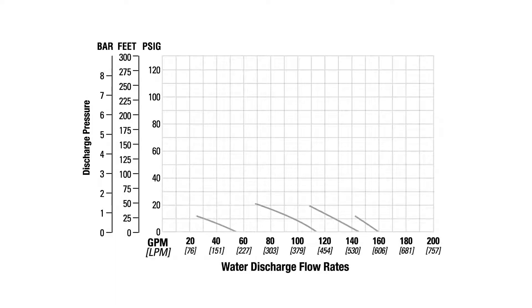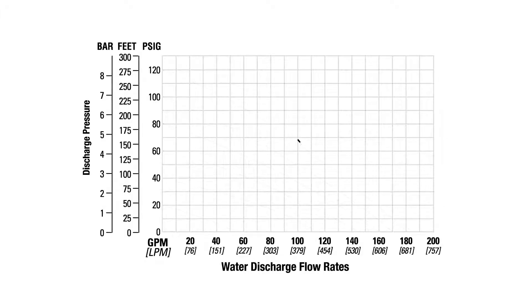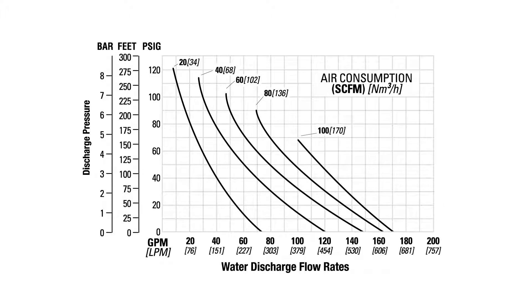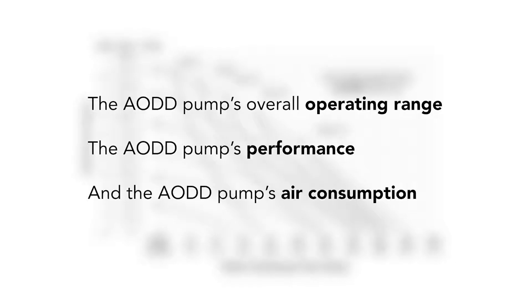The gray curved lines connecting the horizontal axis to the vertical axis represent the pump's air inlet in PSIG. The black vertical curved lines represent the air consumption of the AODD pump, measured in standard cubic feet per minute, or SCFM. There are three main data points an AODD pump performance curve can define: the pump's overall operating range, its performance, and its air consumption.